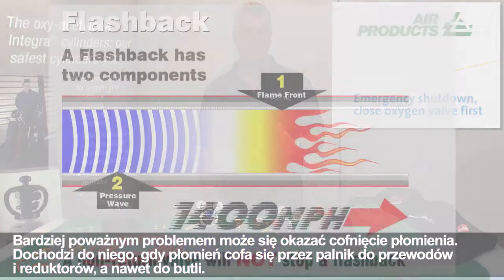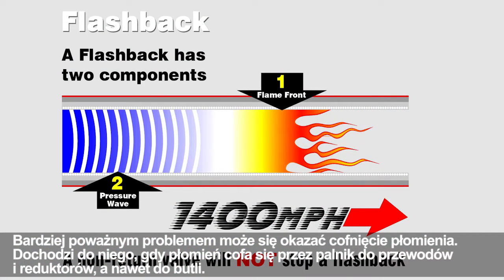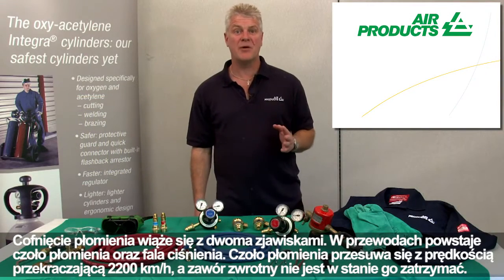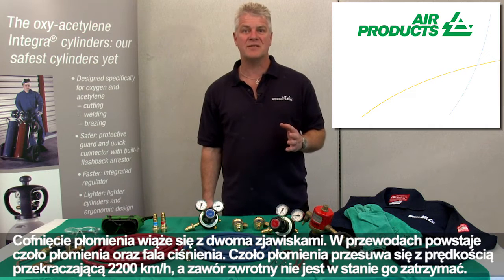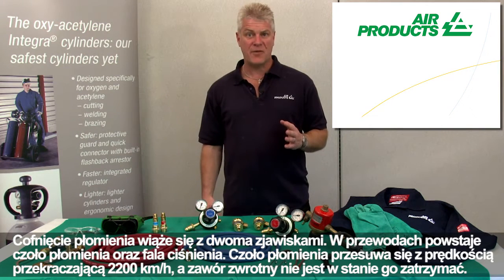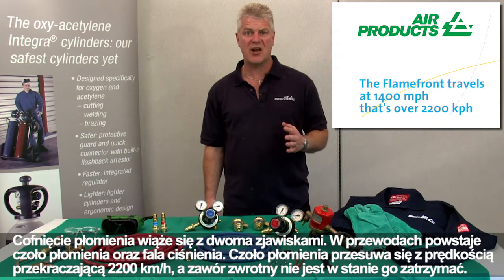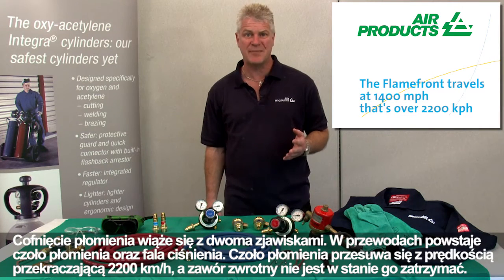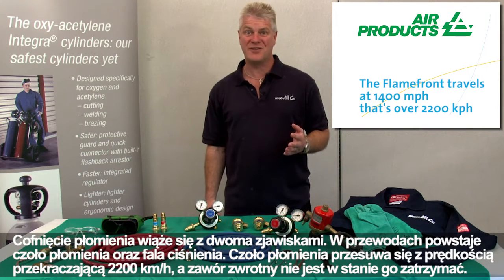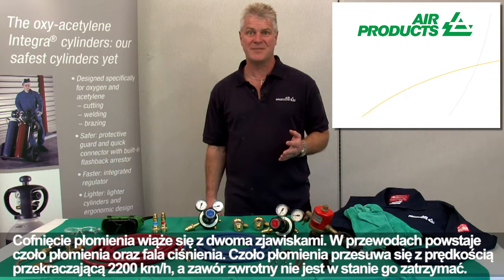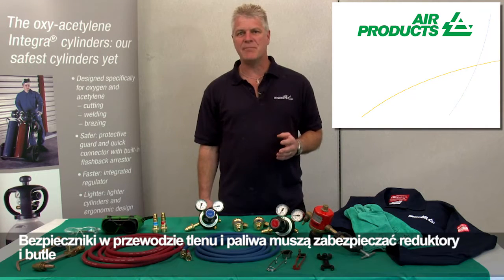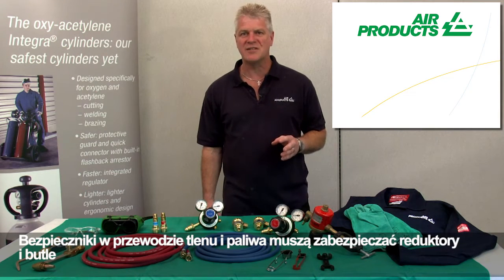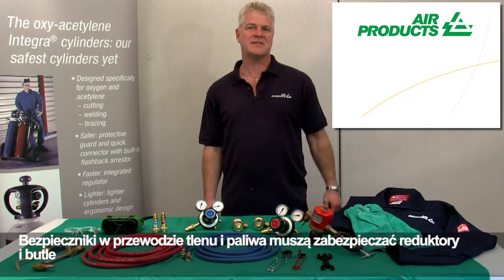This is when a flame front moves back through the blowpipe body into the hoses and the regulators and may also reach into the cylinders. A flashback has two components. It creates a flame front and a pressure wave. The flame front moves with a speed of 1400 miles per hour or over 2,200 kilometers per hour, and a non-return valve will not stop it. Flashback arresters in both the oxy-fuel and oxygen lines must protect the regulators and the cylinders.